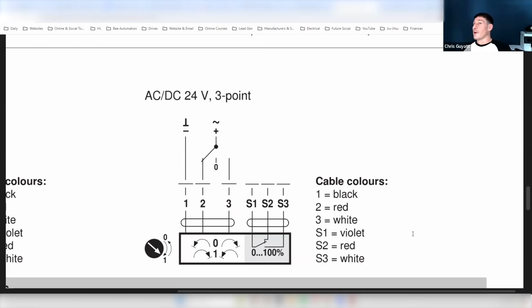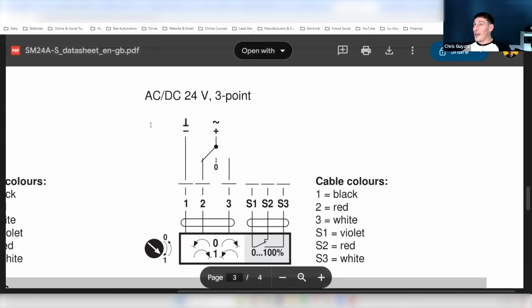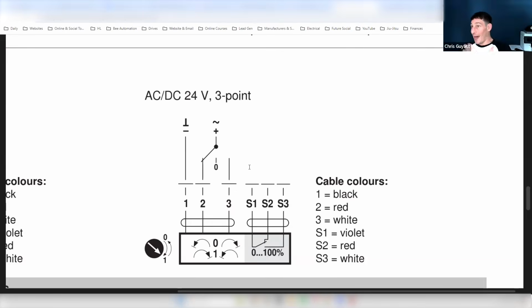Yeah, you could do exactly the same thing using a 0 to 10 volt analog control signal. The same operation would apply. So you apply, let's say, 0 volts, it would be fully closed. 10 volts, it would move to being fully open. 5 volts, it would be 50%. So yeah, there's actuators out there, Belimo actuators, where you can use an analog signal for the control.